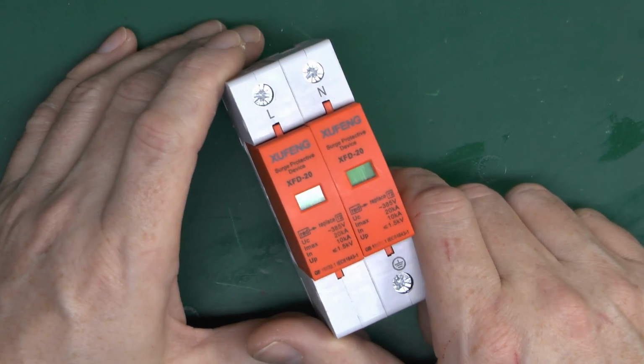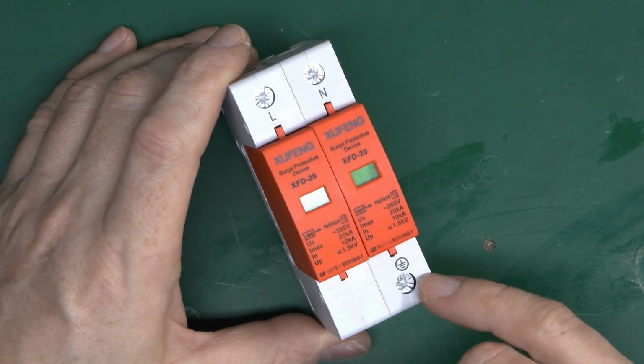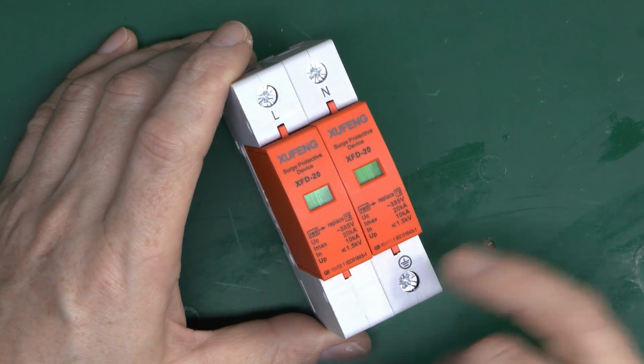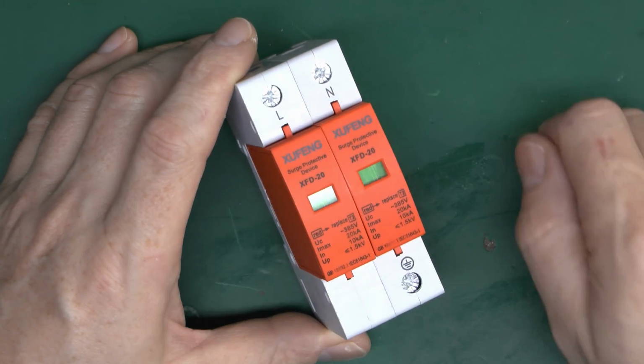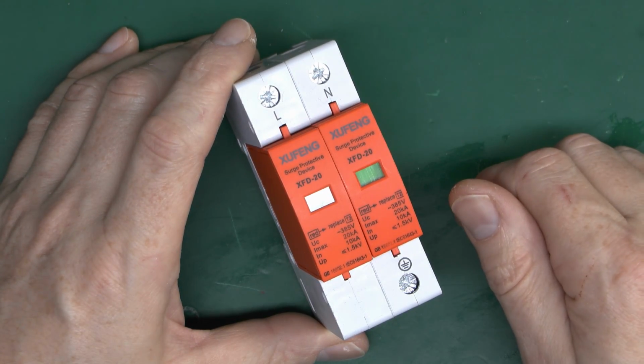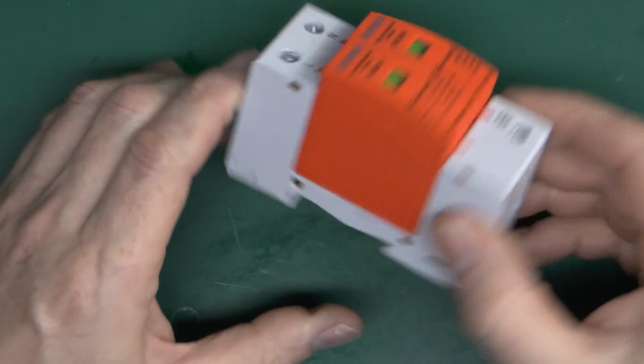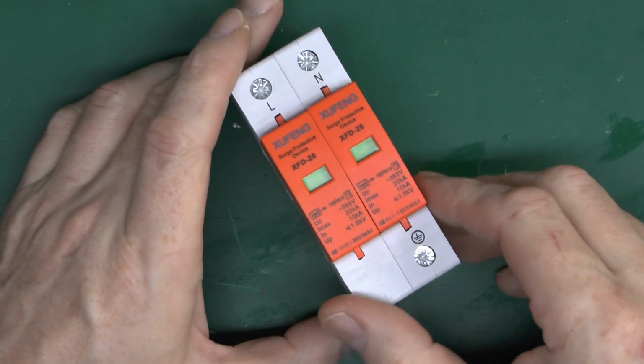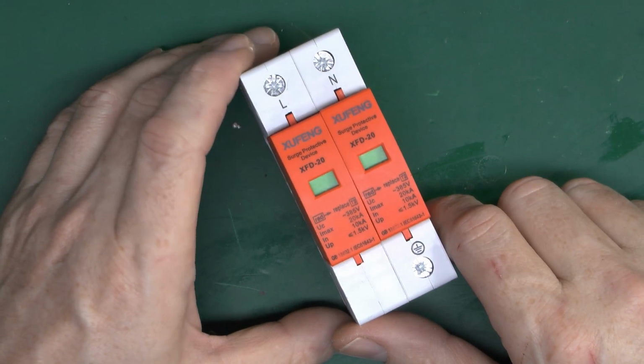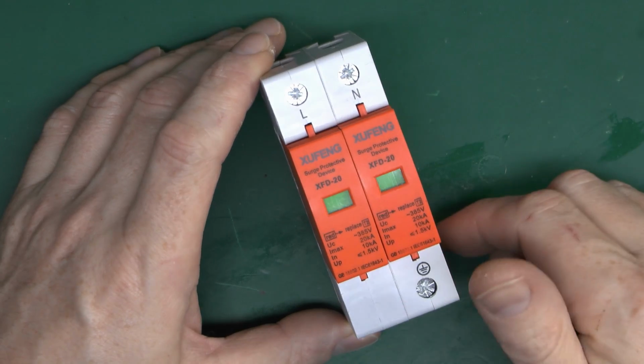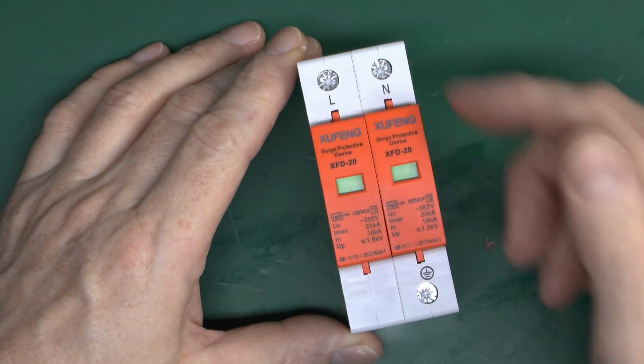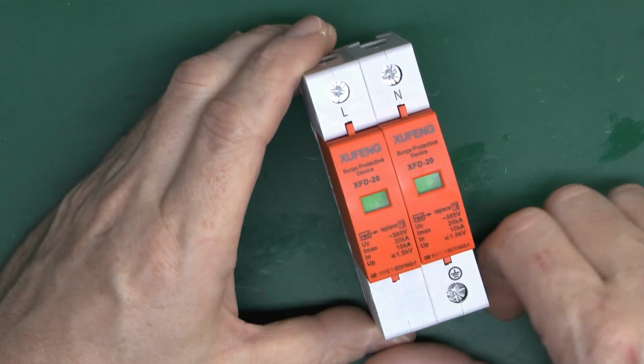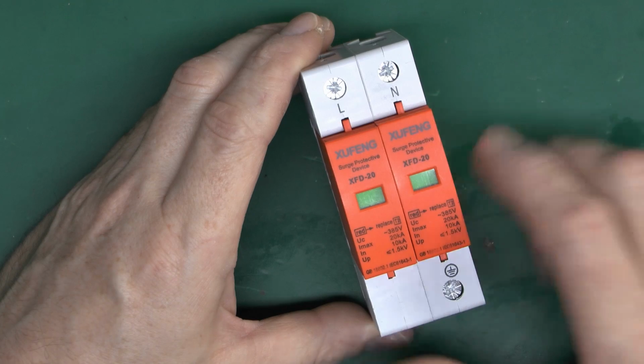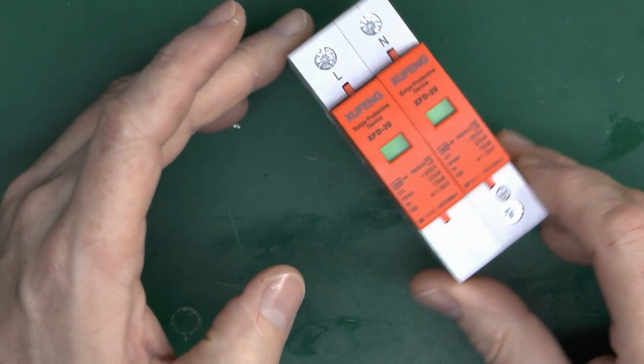Now let's have a look how you would actually install such things. Now, in terms of the electrical connections, it's pretty much the same as any other piece of equipment. On this one we've got the earth here, line and neutral, so it's just 3 wires which connect to those 3 things, generally inside the consumer unit for this style, or in some distribution panel or whatever. You can also put these in a separate enclosure on their own, but in any case it's just the 3 wires there. If you have a 3-phase version of this, then it's pretty much the same, earth and neutral, and then just have 3 line connections, 1 for each phase, rather than just the 1. So again, no real surprise there, pretty much the same as connecting up to any other piece of equipment.